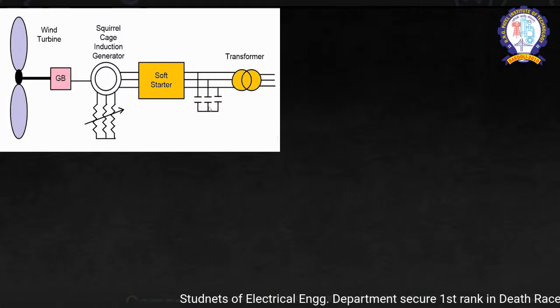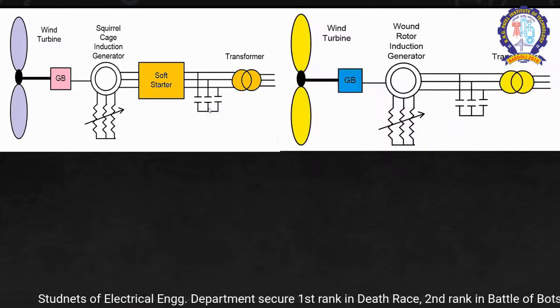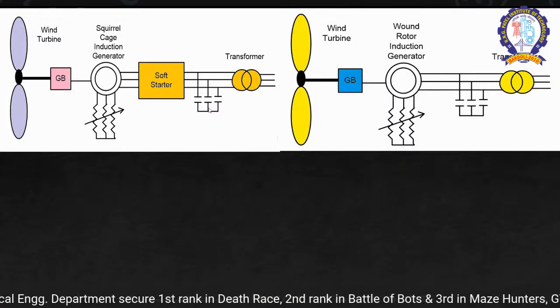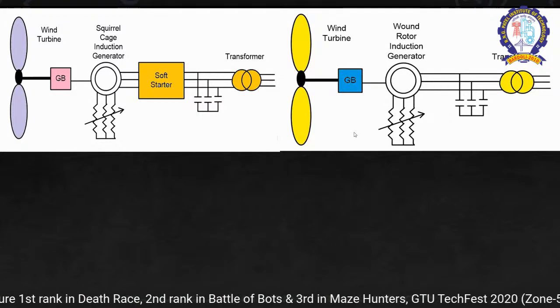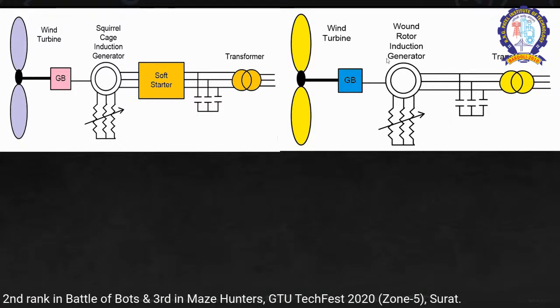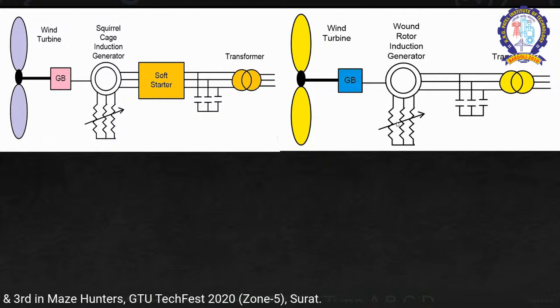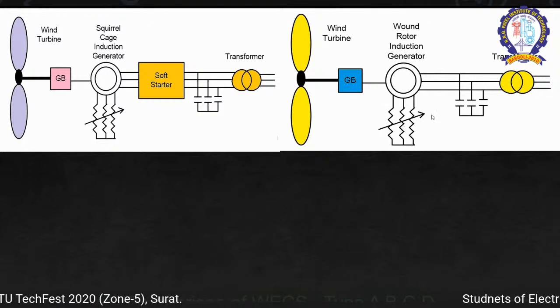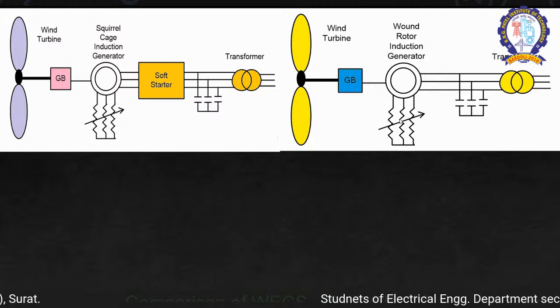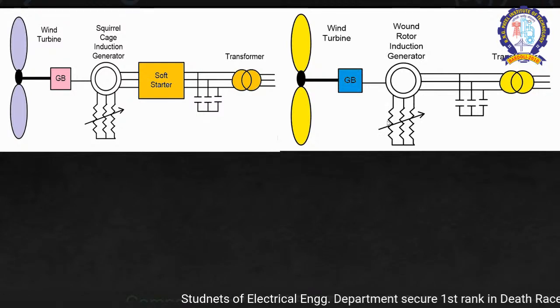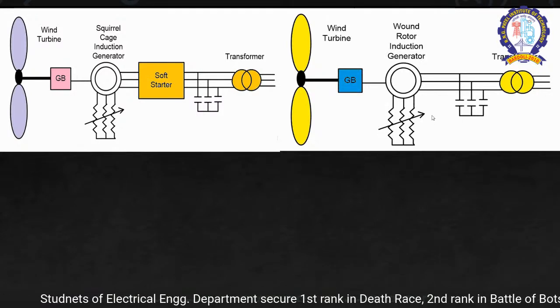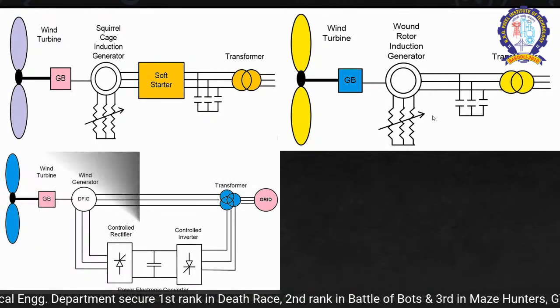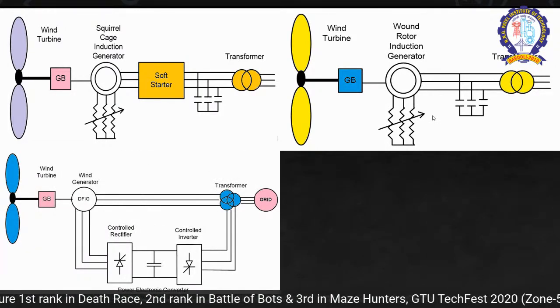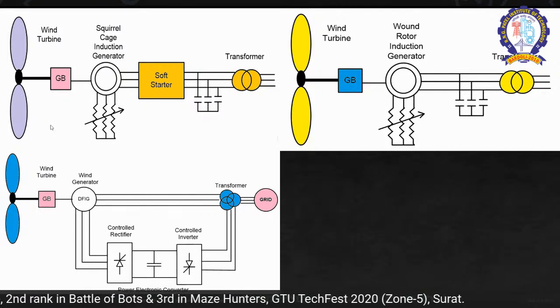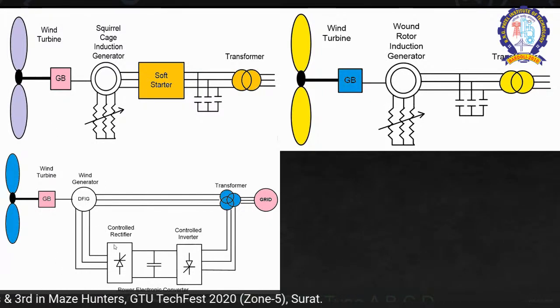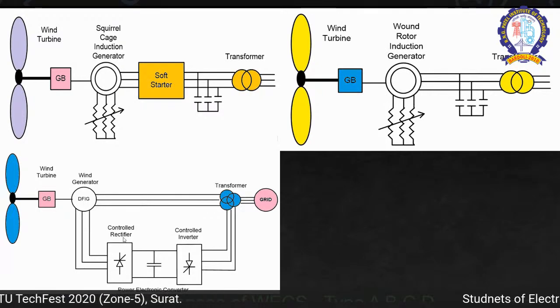This could be achieved in both ways. If you go with the wound rotor induction generator with slip rings, the soft starter is not required because the torque is already controlled using this wound rotor, where the rotor circuit is interfaced with a three-phase resistance. The third aspect is known as the doubly fed induction generator. So the power is fed from both directions. This technology is again renowned for wind energy application.